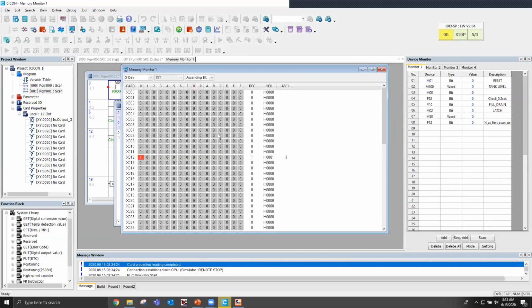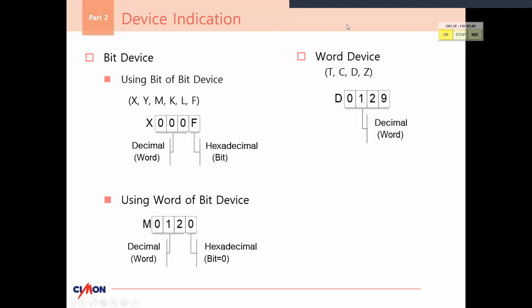Also, you can rearrange the data. If you're used to seeing it from right to left, you can just do descending bit up here if it's better on your eyes. But typically by default, it's ascending bit. On the right side here, you'll see our word registers. We will not see any hexadecimal in the register at all. It will only ever be decimal verbiage because we don't actually talk to the direct bits when we do the word devices. So these will be our T, C, D, and Z registers, different from these registers over here.